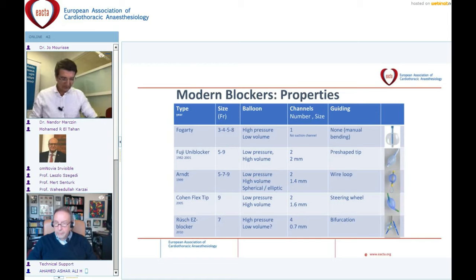Properties of the most frequently used blockers are shown on this slide. Most blockers have low-pressure, high-volume balloons — except for the Fogarty and the EZ blocker, which are high-pressure and low-volume. There is also variation in the diameter of the internal channels. The EZ blocker has the smallest channels, at just 0.7 mm to serve as a suction channel, and some experts question the possibility of applying suction with it.